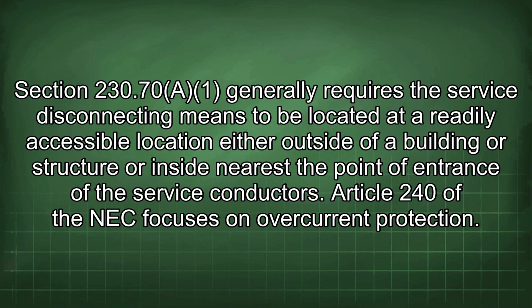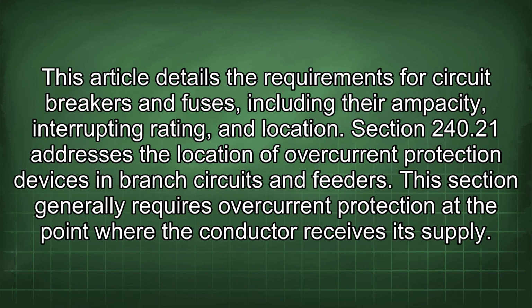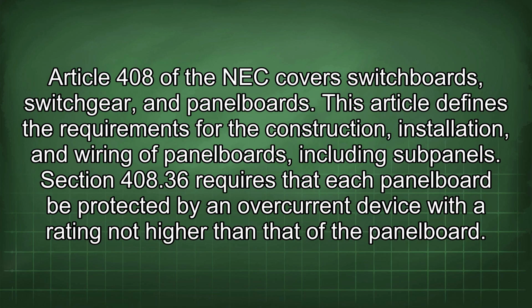Article 240 of the NEC focuses on overcurrent protection. This article details the requirements for circuit breakers and fuses, including their ampacity, interrupting rating, and location. Section 240.21 addresses the location of overcurrent protection devices in branch circuits and feeders. This section generally requires overcurrent protection at the point where the conductor receives its supply. Article 408 of the NEC covers switchboards, switchgear, and panelboards. This article defines the requirements for the construction, installation, and wiring of panelboards, including subpanels. Section 408.36 requires that each panelboard be protected by an overcurrent device with a rating not higher than that of the panelboard.